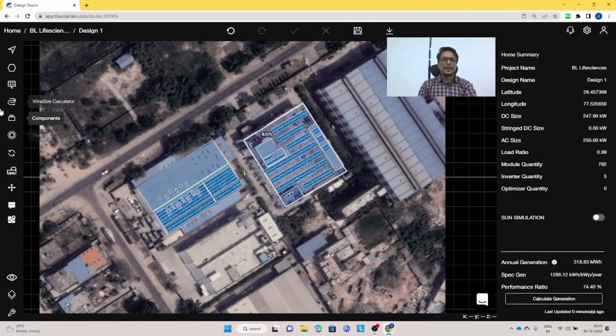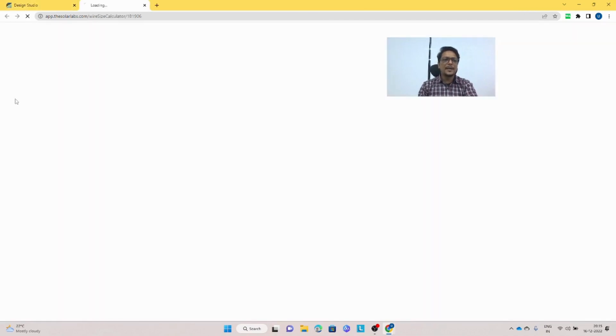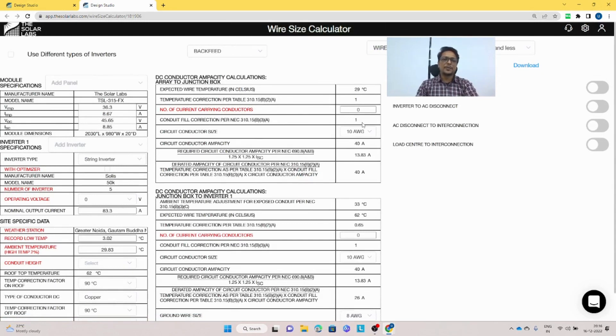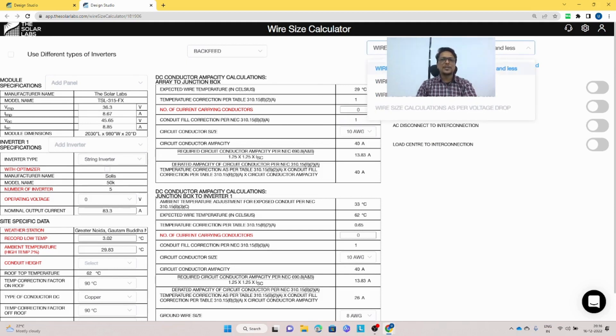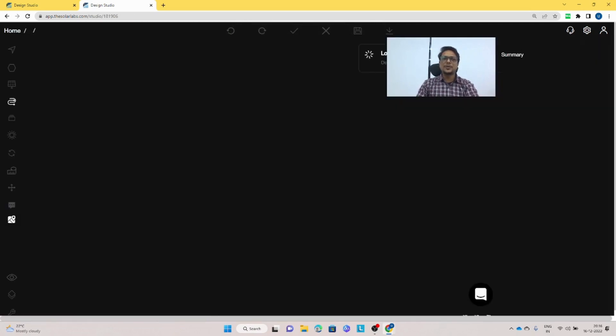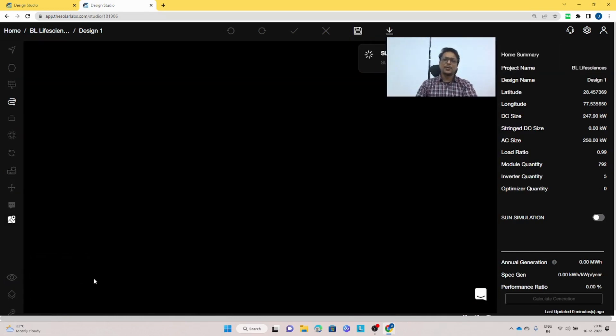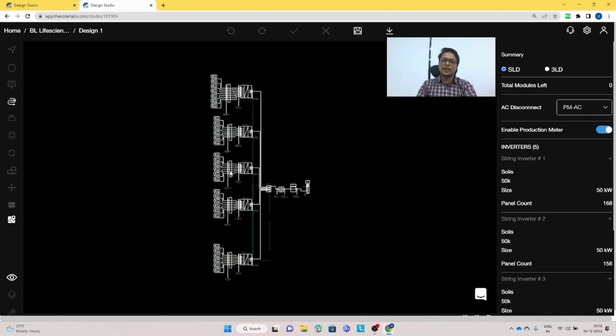Next comes the SLD. We have a wire size calculator opening now. You need to save the wire size calculator to generate the SLD — every time you need an SLD you must save it first. You can change parameters like number of current-carrying conductors and conductor size. This wire size is calculated per NEC standards — 2014, 2017, and 2020 are considered. Once the wire size is saved, click on Studio and then go to View and Line Diagram. The SLD will be shown and can be exported as CAD for any necessary changes.